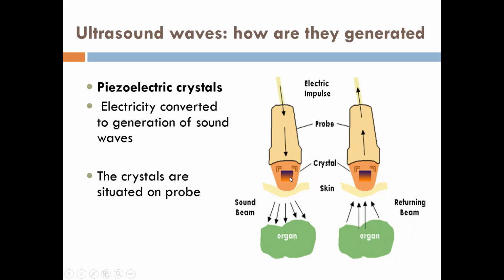Depending upon the quality of the piezoelectric crystals, different frequencies of ultrasound waves are emitted from them. And depending upon the density of the various structures in the body, these sound waves will travel to the distant organs. The waves get absorbed to some extent, and to some extent they get reflected. Because of the absorption of some of the ultrasound waves and reflection of the remaining waves, these waves return back and create an image on the display. So this is the basic principle of any ultrasound machine.